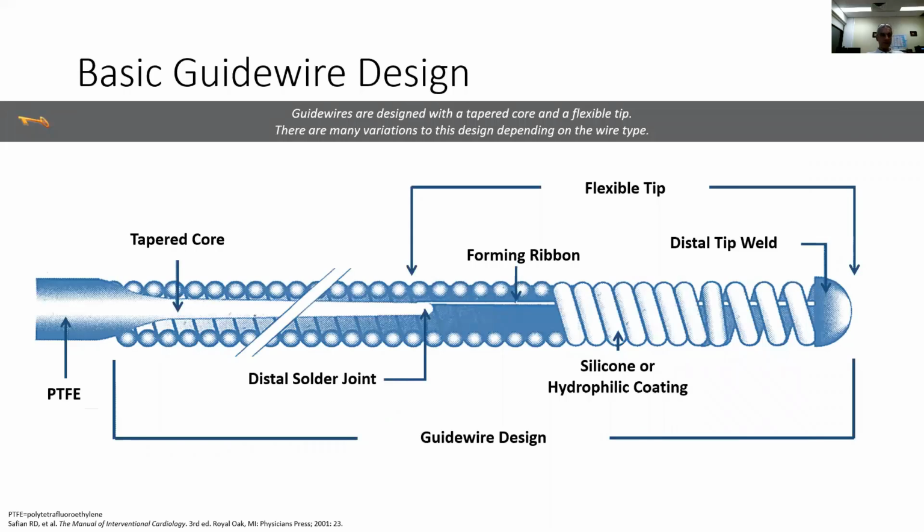And similarly with the guide wires, a catheter sometimes can get floppy like a loop of spaghetti, and the cardiologist loses control. When he does, he inserts a wire, which is more than just a thin coat hanger. You can see the design. It has an internal tapered core with kind of like a helical construction of a very fine wire forming a flexible structure on the outside. And you can see by the distance between each coil, it can give a twistability. And the distal tip has to be very soft and rounded to protect the inside of the vessel. Even so, we still have injuries and dissections.